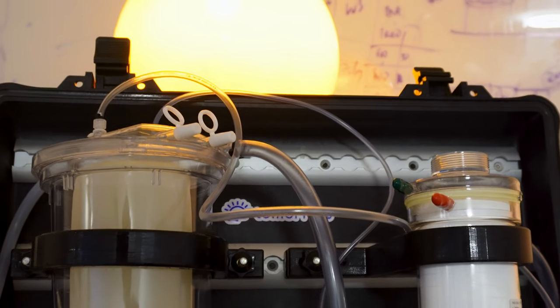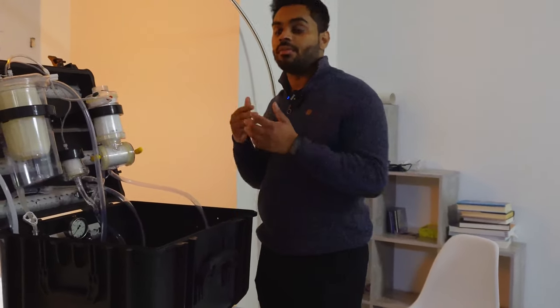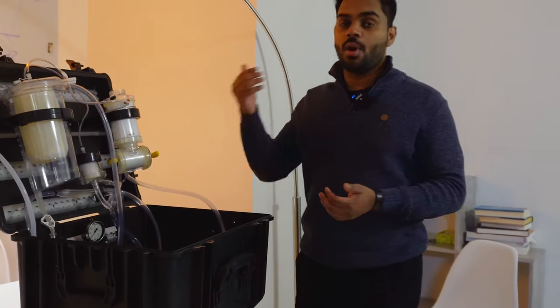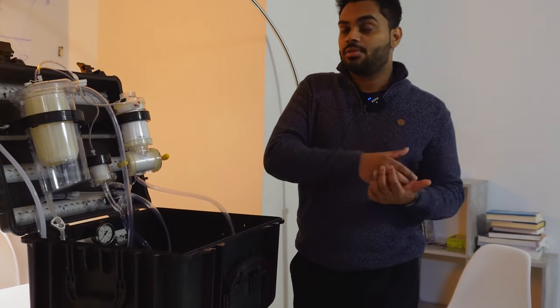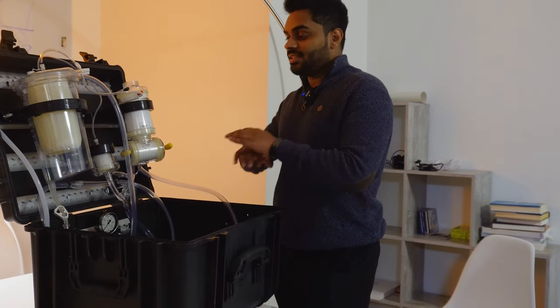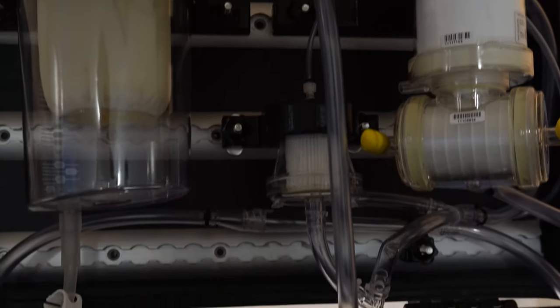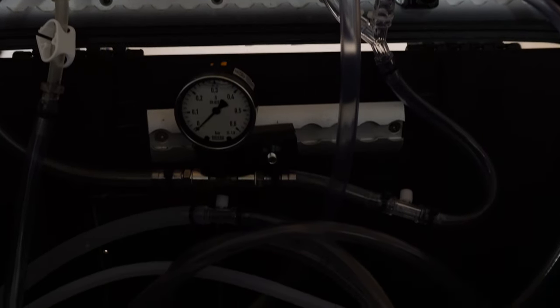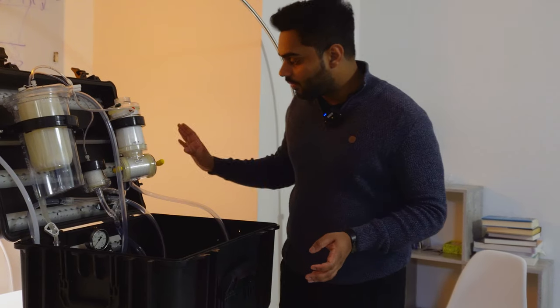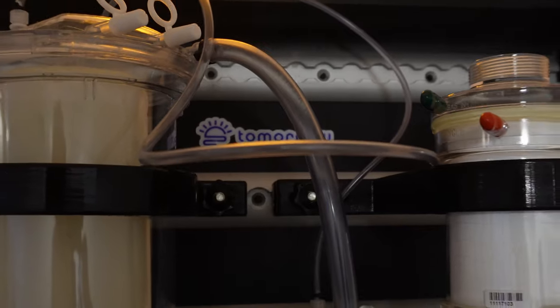This is another cool piece of equipment I get to work with — this is actually a mobile perfusion system. We use this system on cases where we wouldn't take the ambulance, in situations where we want a fast response vehicle to go ahead in front of the ambulance. If the ambulance is still too slow, we can start the whole cryoprotection procedure just with this perfusion system. It's just like the one in the ambulance, fitted with every single part, only in a compact form. You have the blood reservoir here where the cryoprotectant would go, all the filters, including even the bubble traps, which make sure that there are no bubbles when we cannulate the large vessels to perfuse the cryoprotectant.